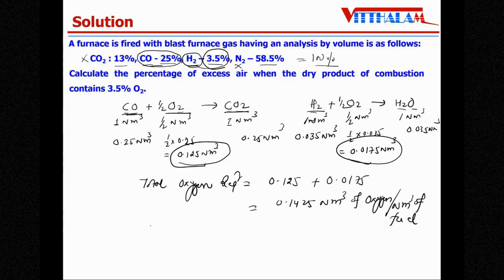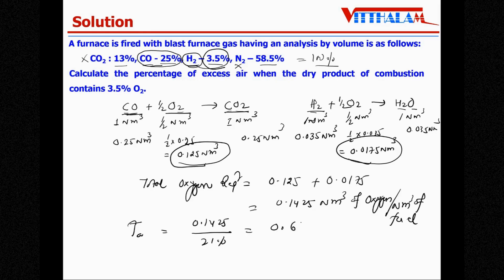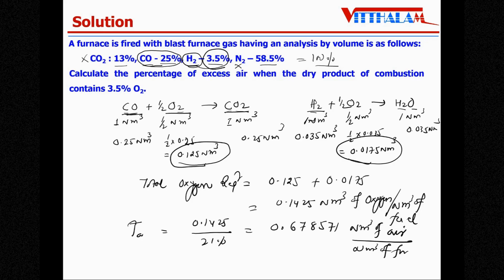Therefore the theoretical air or stoichiometric air is: 0.1425 ÷ 21% = 0.678571 nm³ of air per nm³ of blast furnace gas fuel. This is the first answer — theoretical air per nm³ of fuel.